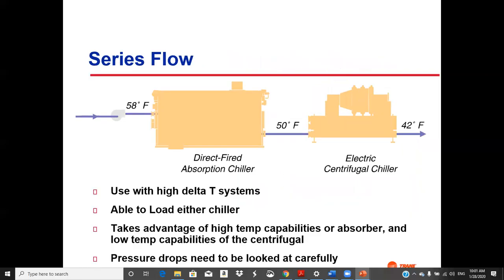This is series. Operationally, this is much more flexible, in that you put all of the chilled water through the absorber, and then you put it through the electric centrifugal chiller. There are some characteristics down here. The big downside of this is you've got the pressure drop going through this one, and you've got the pressure drop going through this one. So you're kind of always paying a double pressure drop.